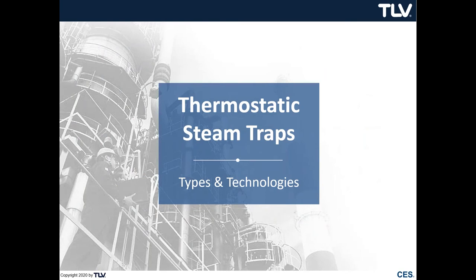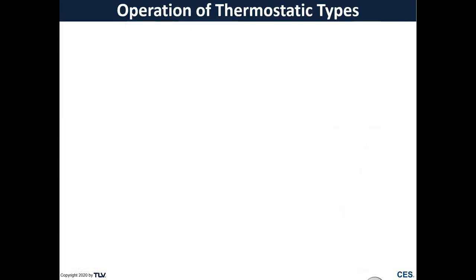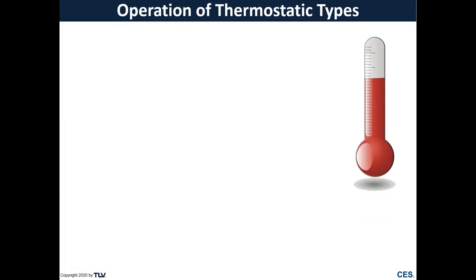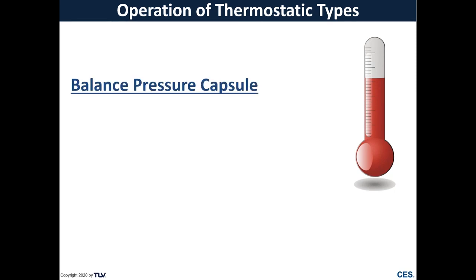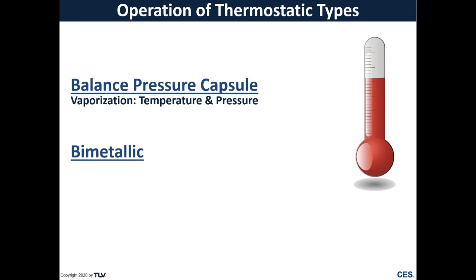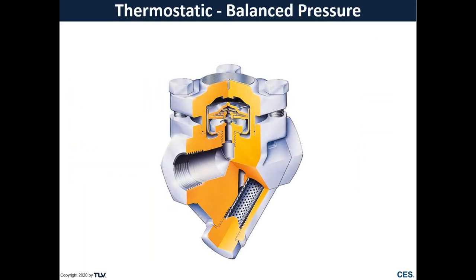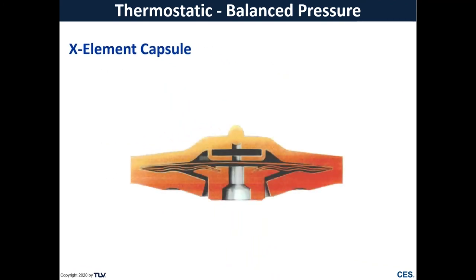The first trap type I'd like to cover is the thermostatic steam trap. The operating principle for these traps is temperature. So we're going to cover balanced pressure capsules, which operate on temperature as well as pressure, and then the bimetallic trap, which operates solely on temperature. So let's take a look at one of TLV's balanced pressure traps. The main component here is our X element capsule. I'll cover what that is.